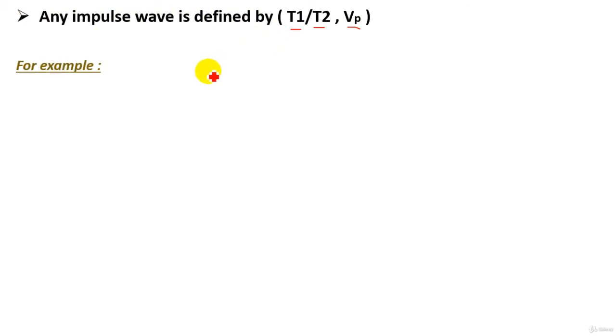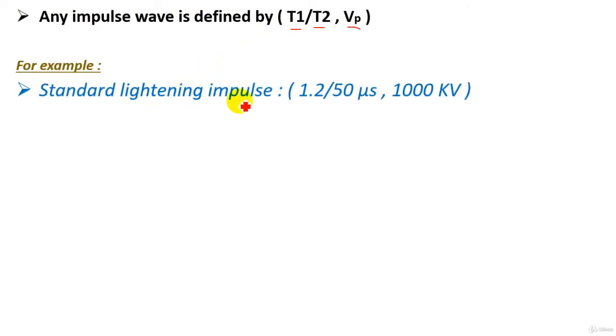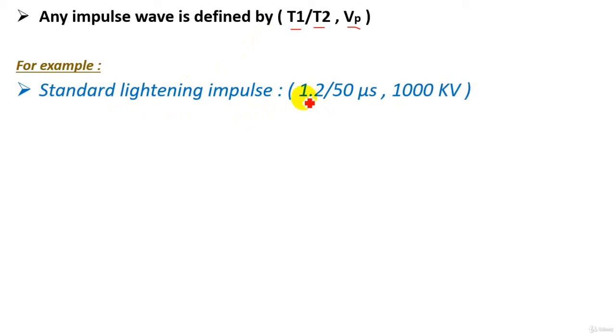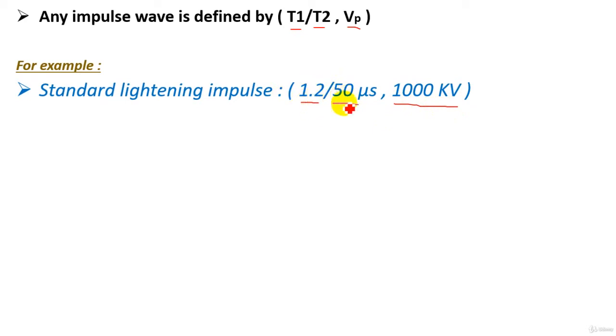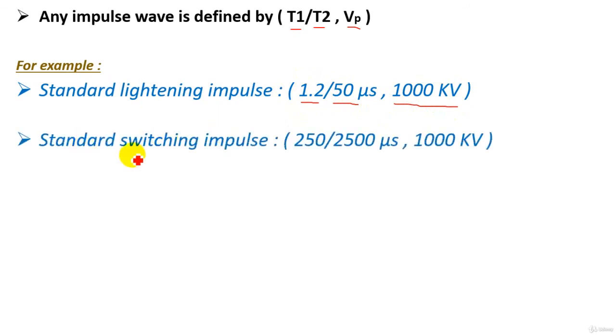For example, the standard lightning impulse that can be produced in a high voltage lab should have the following characteristics: a waveform of 1.2/50 microseconds and 1000 kilovolts. That means the rise time is 1.2 microseconds, the tail time is 50 microseconds, and the peak voltage should reach 1000 kilovolts.